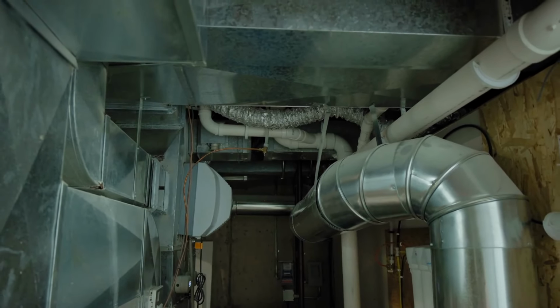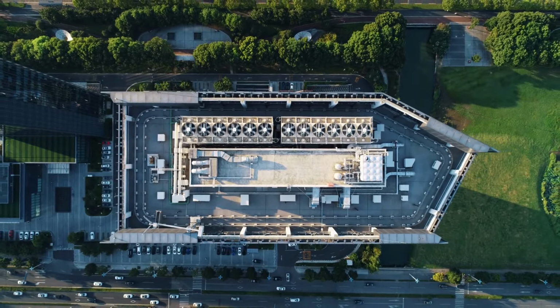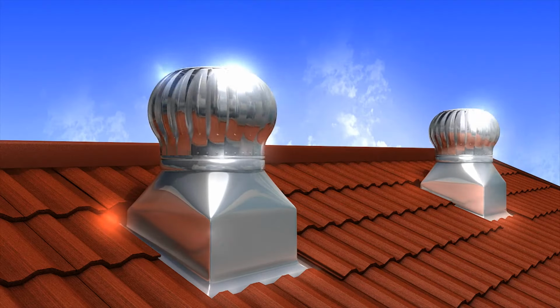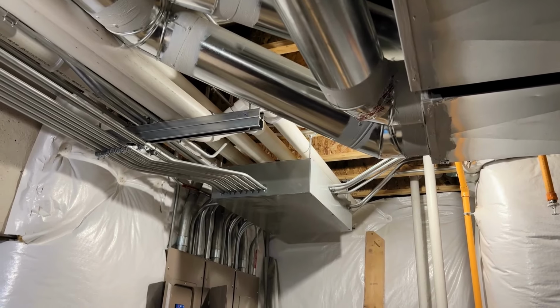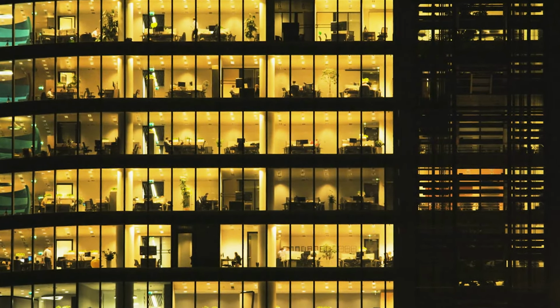In fact, the CDC recommended that last year, and the air conditioning peak body, ASHRAE, also recommended higher levels of ventilation. That higher level of ventilation basically flushes those pathogens out. Obviously, you've got to have a source of fresh air to come in, and you've got to be able to exhaust it out. They've moved that from about 3 air changes per hour in a good building. Believe it or not, 3 air changes is all you get, and that's good ventilation. There are many places where it's down to 1.5 and 1, and that's really where you get sick building syndrome and you're feeling sleepy. The carbon dioxide levels go up.